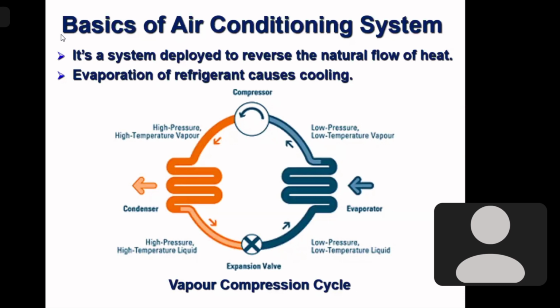So we take out that heat by passing the hot refrigerant gas through a coil and cooling that coil, which is also called the condenser. We can cool that coil either by air or by water. When we cool the condenser coil by air, we call it an air-cooled condenser, and when we cool it by water, we call it a water-cooled condenser. The refrigerant which comes out from the condenser coil is now a little colder, a high pressure, high temperature, liquid kind of refrigerant. Then we pass it through an expansion valve, which expands the refrigerant when it passes through it. Sudden expansion of refrigerant causes cooling. It becomes gas and it gets cold. The cold refrigerant is then passed through another cooling coil, which is called the evaporator, where the refrigerant is in the form of cold gas and a little bit of cold liquid.